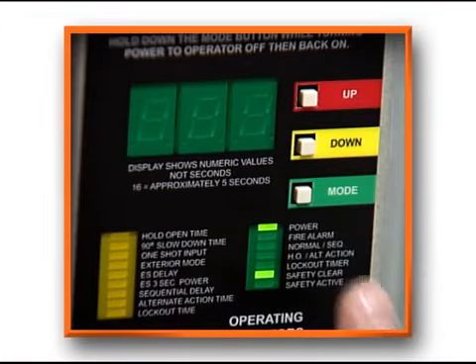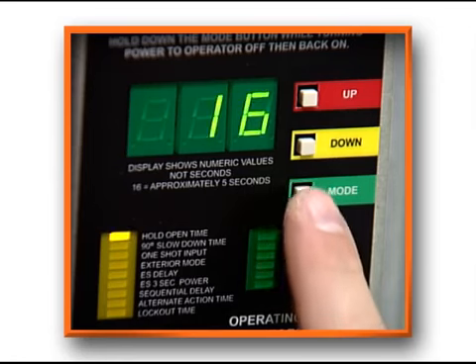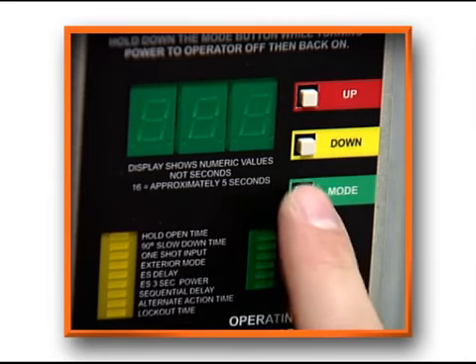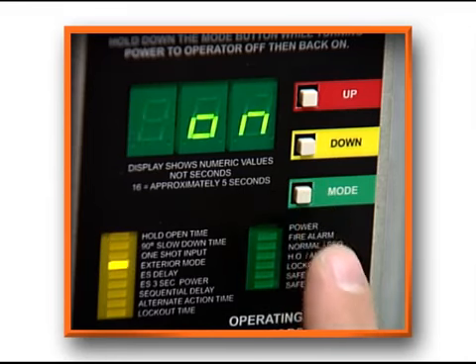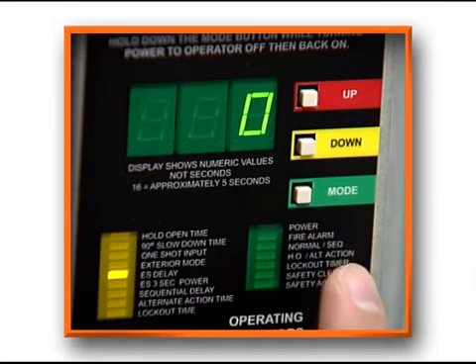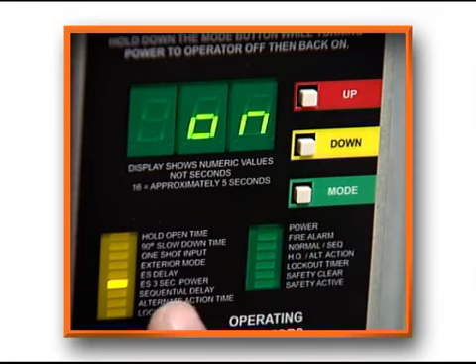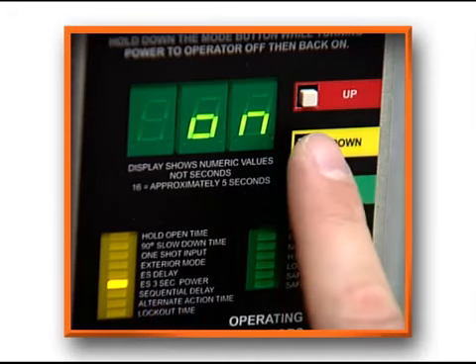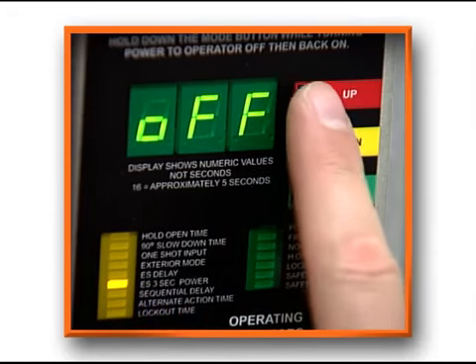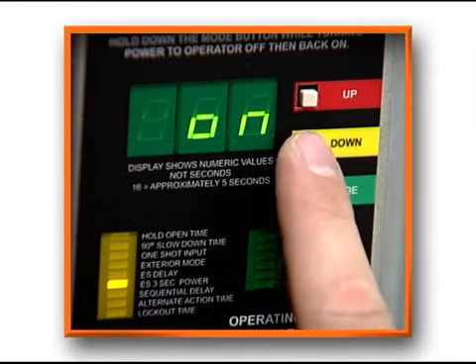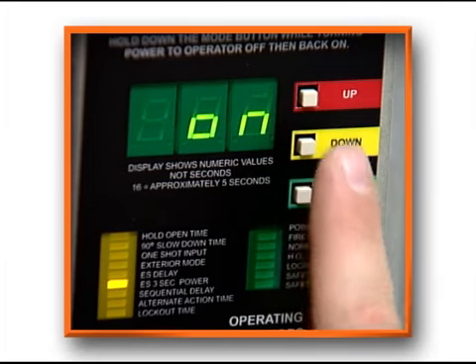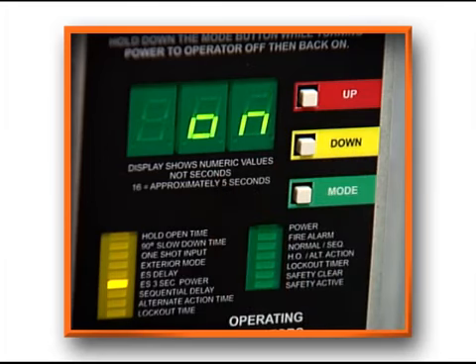The ES 3-second power is an on or off option. If off, the ES relay is powered the entire opening cycle and hold open time when the door is open at 90 degrees. It releases when the door starts to close. If this option is switched on, the ES relay is powered for only 3 seconds after the door is activated, then it releases. The default is on.